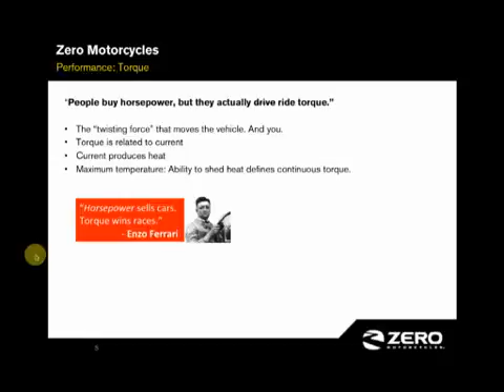Unfortunately, that current produces heat. The more current, the heat actually goes up with the square of the current that goes in. So you double the torque, you produce 4 times the heat. And that maximum temperature is where you determine how much torque your motor can produce continuously. It comes down to how much heat you can remove from the motor, and that defines how much continuous torque you can produce.